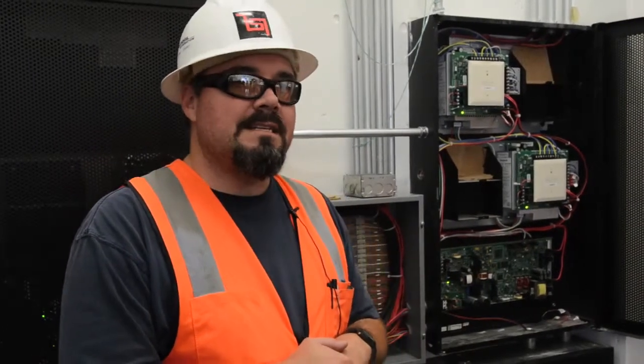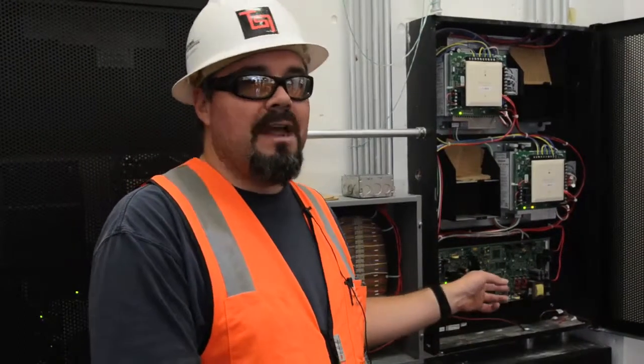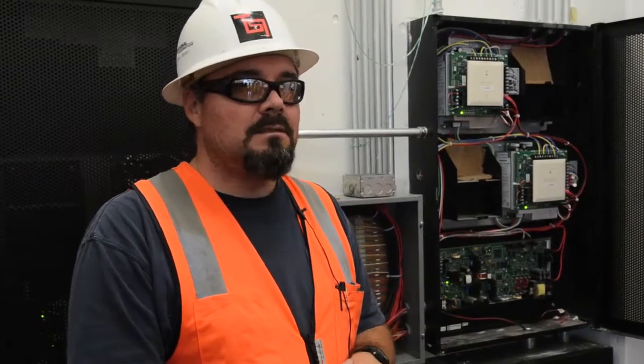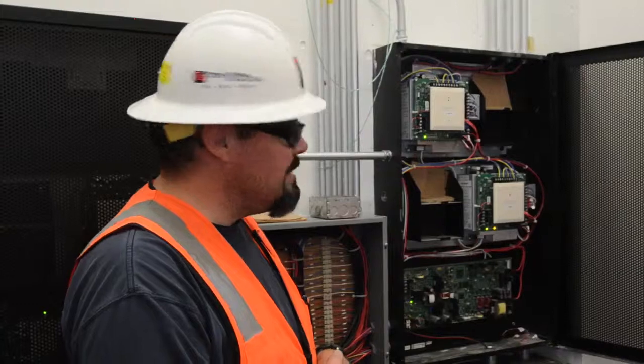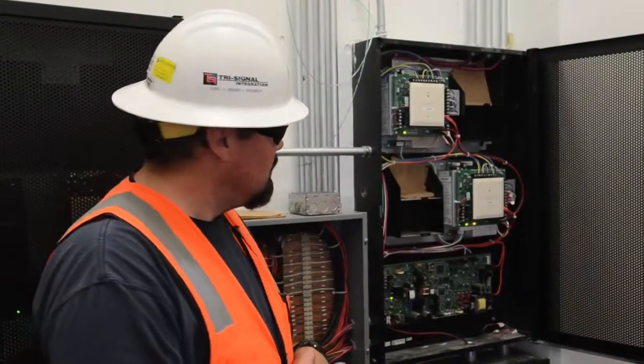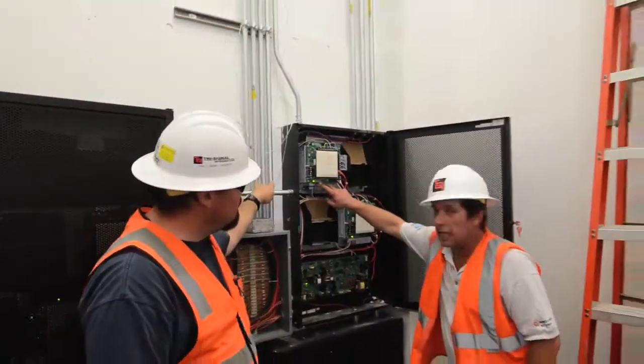You're not able to put announcements or any kind of voice over a horn. Usually that's just the device itself. You can just put 24 volts to it and it's going to do it automatically. Here we have to program the speakers to make the announcement. That's why it matters for troubleshooting purposes, because sometimes they'll tell you the whoop doesn't work but this does. Right, sure. So it's a little bit different animal, but it's the same lines, just more advanced speakers, because the typical ones just make the whoop noise. One of the nice functions of these power supplies is they actually have memory. Here you have trouble indications for each circuit.